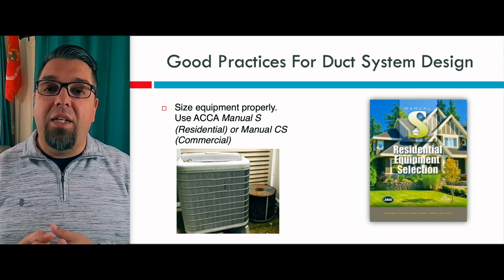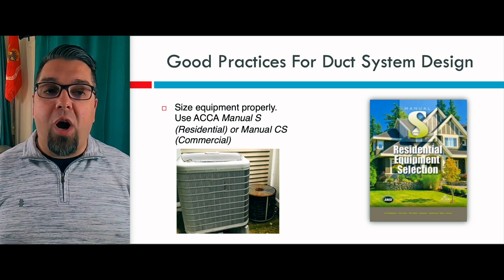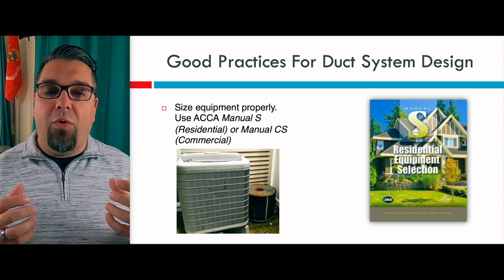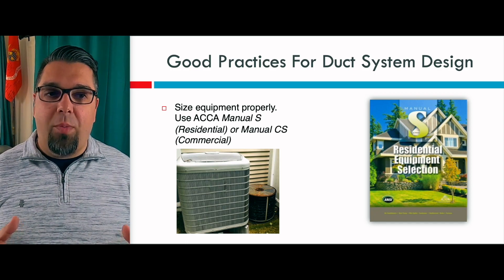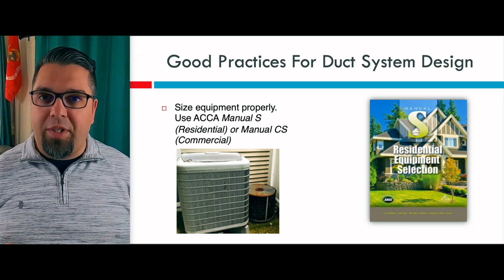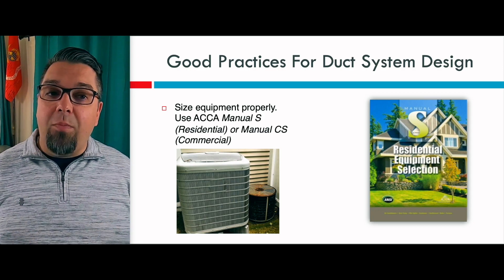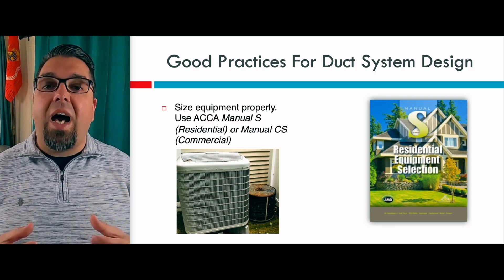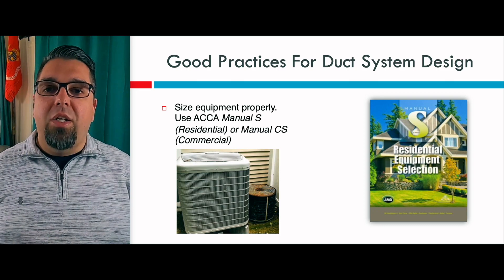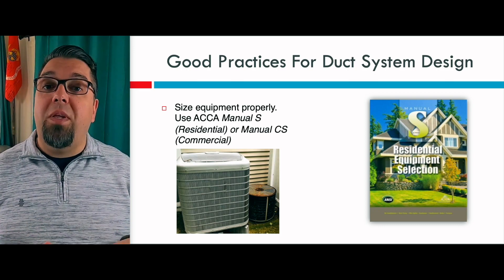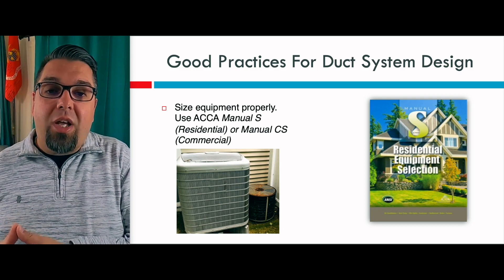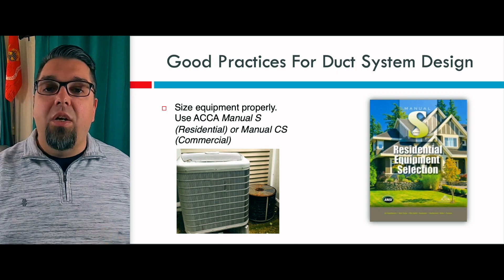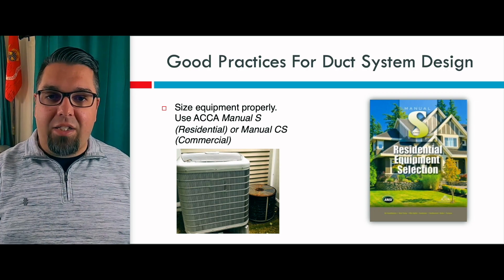The next step in the system design is to size the equipment properly. We cannot fix the duct system or change the duct work if you don't have the right size piece of equipment — it's not going to fix the real problem in the house. You're going to use ACCA Manual S for residential applications in order to accurately size your equipment based on the load calculation. If you're doing commercial, this would be Manual CS — so you do a Manual N load calc, then Manual CS for commercial sizing. For residential, it's Manual J, then Manual S for sizing.